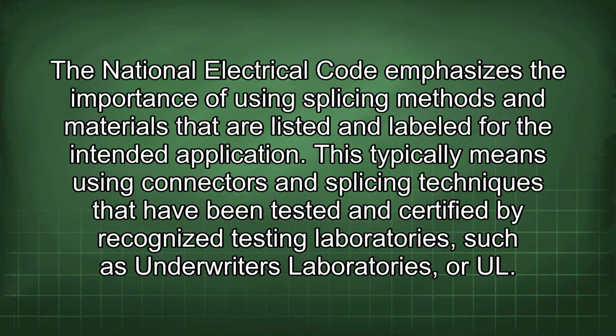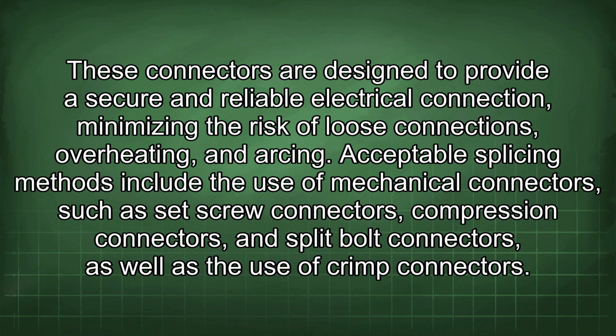The National Electrical Code emphasizes the importance of using splicing methods and materials that are listed and labeled for the intended application. This typically means using connectors and splicing techniques that have been tested and certified by recognized testing laboratories such as Underwriters Laboratories, or UL. These connectors are designed to provide a secure and reliable electrical connection, minimizing the risk of loose connections, overheating, and arcing. Acceptable splicing methods include the use of mechanical connectors such as set screw connectors, compression connectors, and split bolt connectors, as well as the use of crimp connectors.